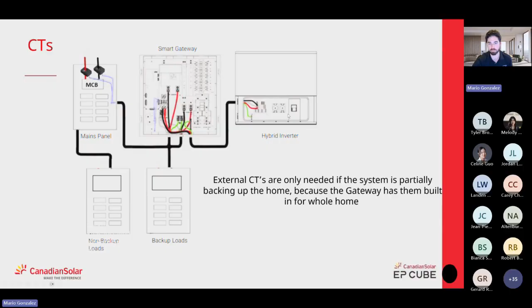This is for a partial configuration, showing where to install the CTs. Very important: if you have a main service breaker or panel that splits into two panels, you always want to put the CTs between the breaker and the meter. This is critical because it's what monitors the entire system and the energy flow. If you put the CTs in the wrong place, the readings on the app won't make sense, and the homeowner won't be happy because what he sees in the app won't match what's actually happening with the system.